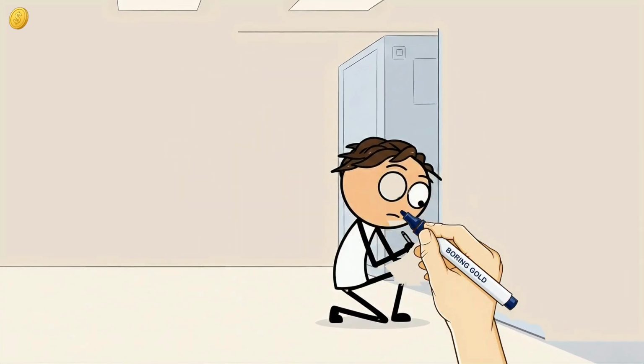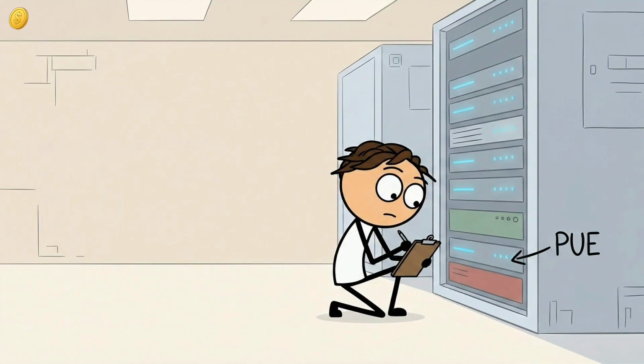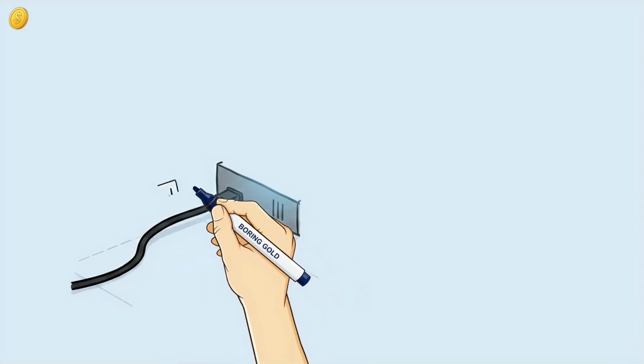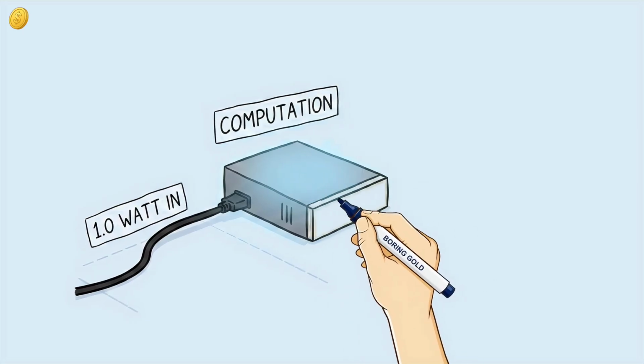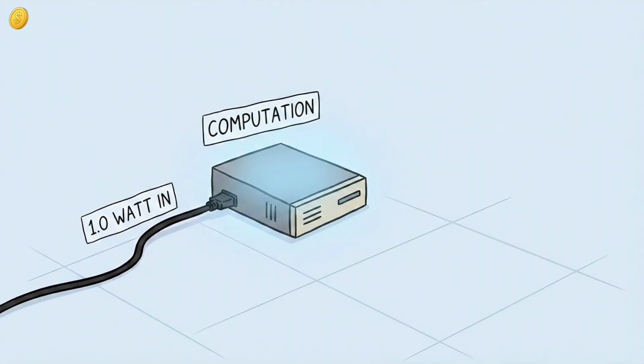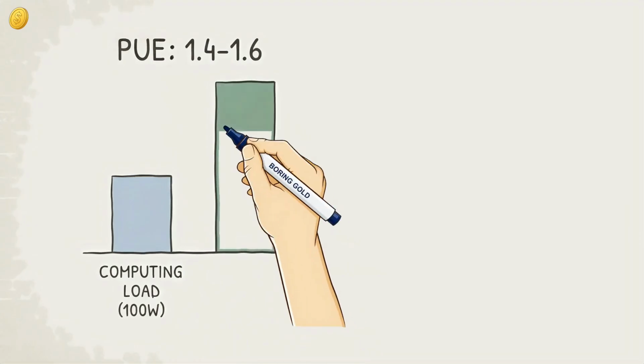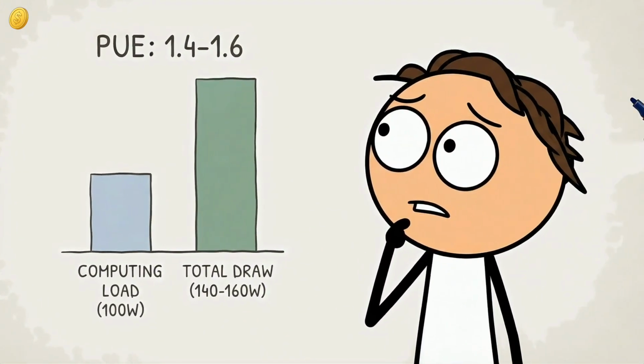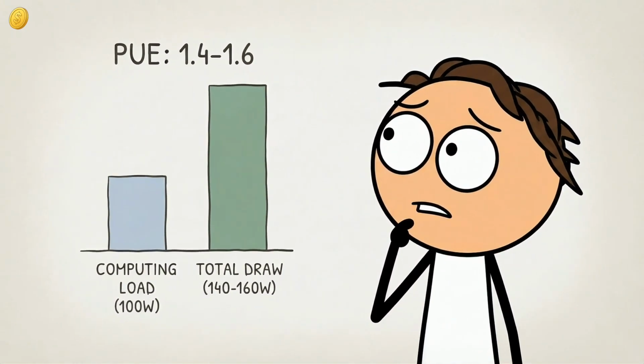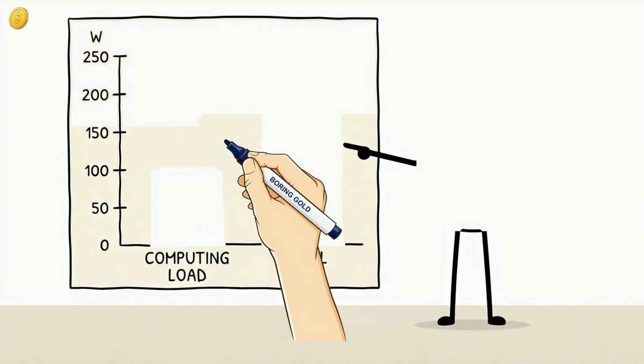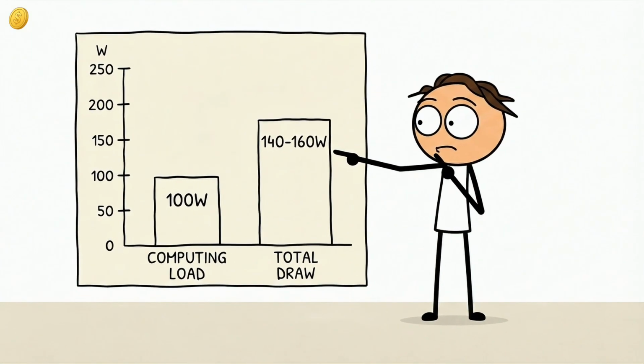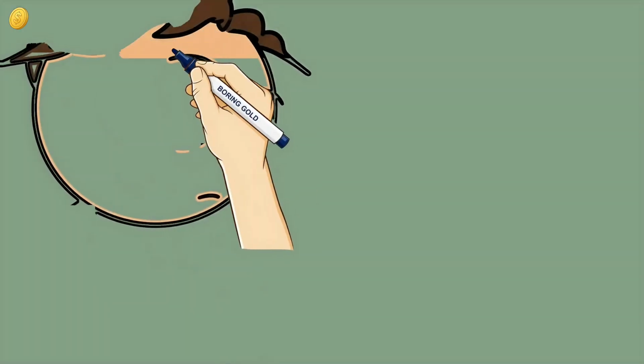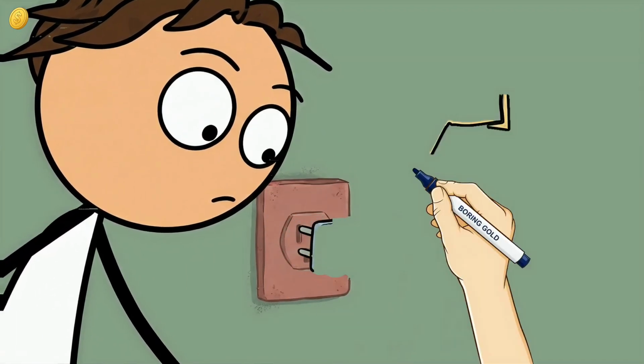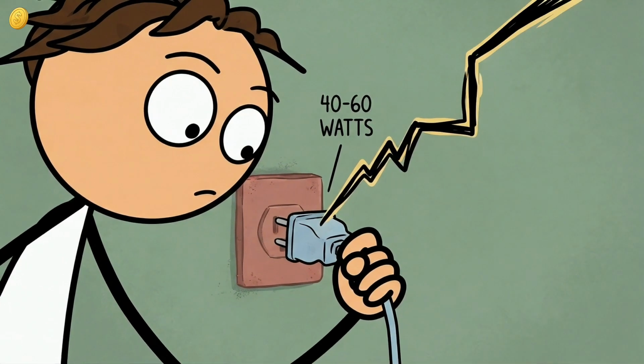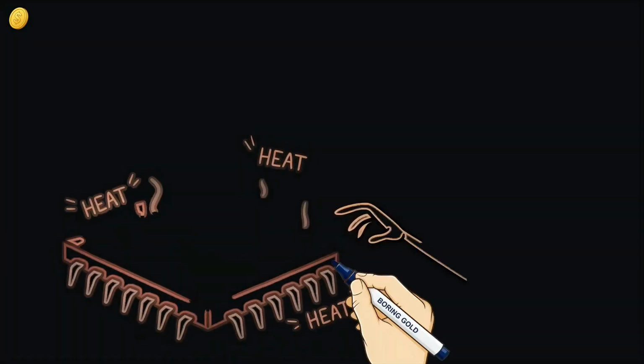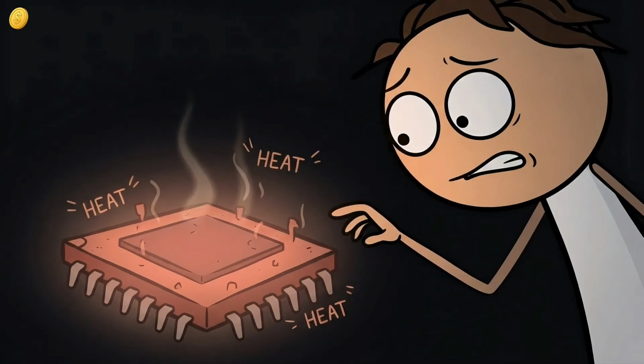The industry measures cooling efficiency using power usage effectiveness, or PUE. A perfect PUE of 1.0 would mean every watt drawn from the grid goes directly into computation. A good air-cooled facility achieves a PUE of around 1.4 to 1.6, meaning that for every 100 watts of computing load, the facility draws 140 to 160 watts from the grid in total. That additional 40 to 60 watts goes entirely to cooling and overhead. It never touches a GPU. It never trains a model. It exists solely to prevent the GPUs from turning into expensive slag.